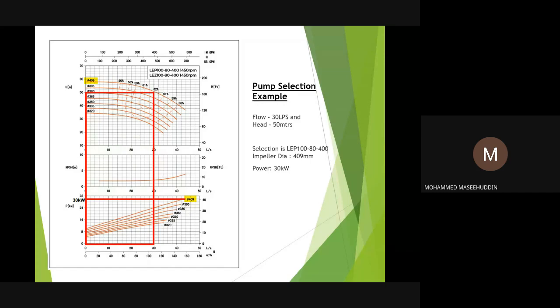So we need to take care, when we are selecting the pump, that it is not only to do with the pump model, but it has also got to do with the net positive suction head, which is more important. And when you look at the power required to run this pump for this duty condition, if you go down on the pump curve, on the motor curve, at 30 liters per second, and on this impeller size of 409mm, it is showing 24 kilowatts.